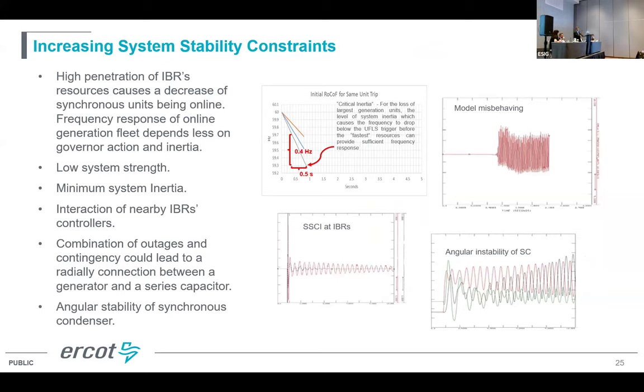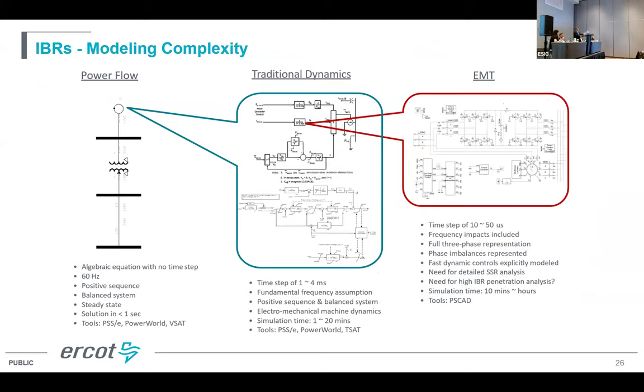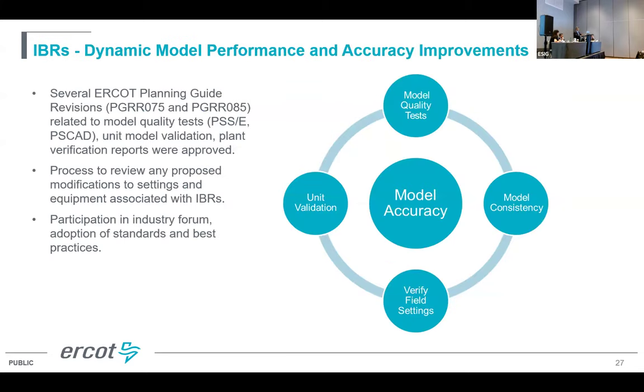I don't have to lay out all these issues. You'll probably hear about oscillations and other things in the next panel or discussions. But some of the issues are mainly driven by low system strength, inertia, and ride-through issues. In terms of modeling, the models are getting more complex. We can't solve this using traditional steady-state or transient stability dynamic studies; you have to go to EMTP-type studies, which we try to do and integrate into our planning process. Modeling is the key: you have to constantly update your models, make sure they are accurate, and validate them based on real-time events. All these things are going on within ERCOT, with many panels and technical discussions happening around this.